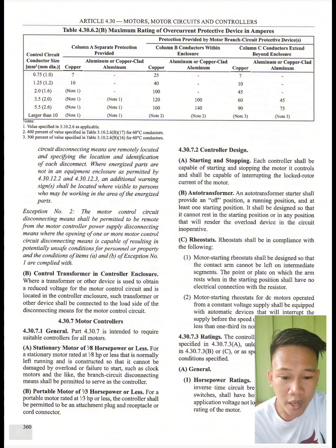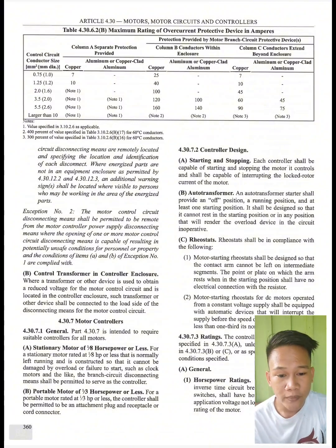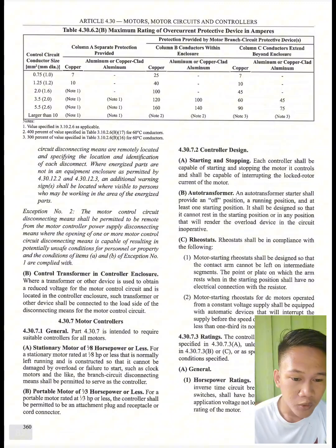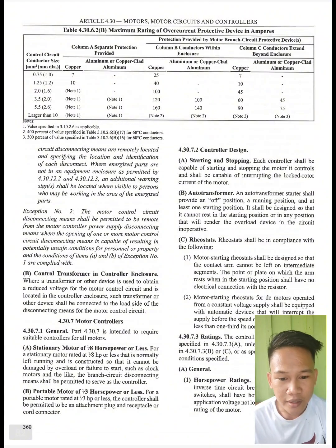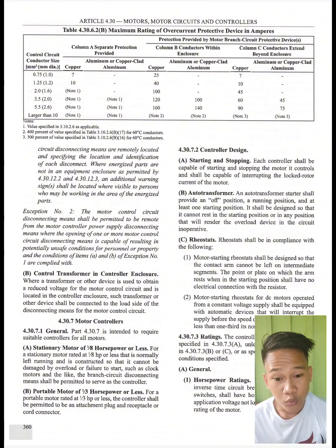So we have here the control circuit conductor size in millimeter squared. So 0.75 or 1, the copper is 7. For aluminum or copper clad aluminum, there is no specification yet. So copper 25. Then for aluminum, still none. So copper 7, for aluminum or copper clad aluminum, none yet. So the 1.25, 1.2, copper 10. For aluminum, none. Then in column B, 40 for the copper. Then in column C, copper 10. Next is 2.0, 1.6. The copper is in note 1. Then in column B, 100. Column C, 45.